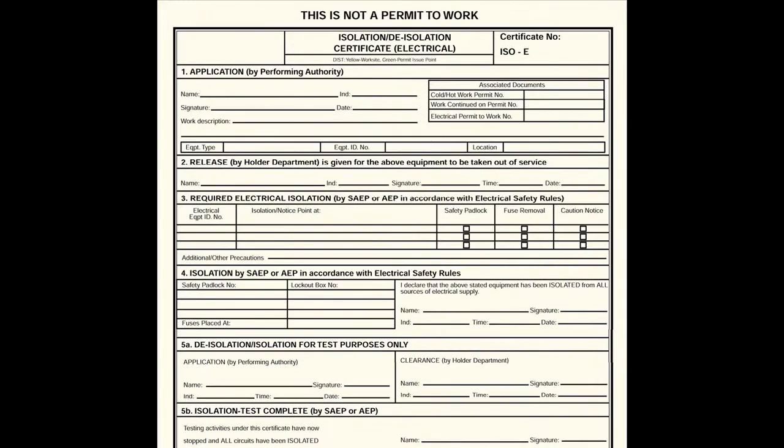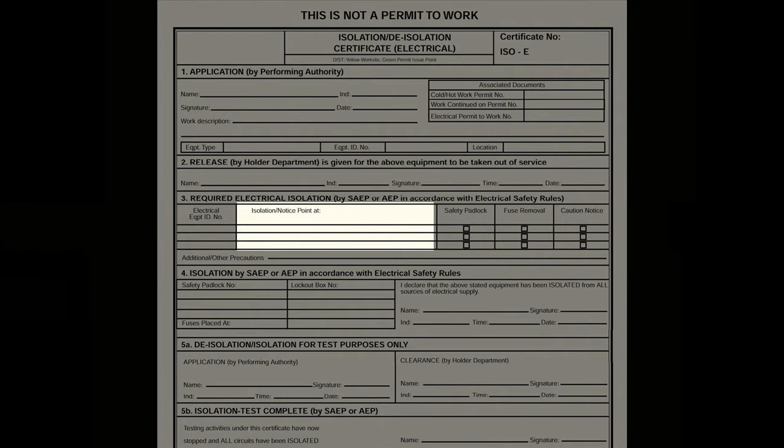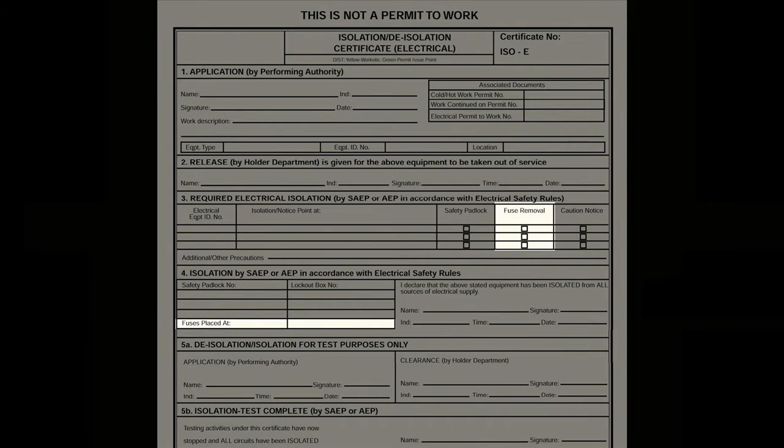The isolation control certificate is used when any isolation is going to take place on a system using high voltage. It is an additional precaution that requires information regarding lock off points, key numbers, fuses removed, and warning labels to be recorded.